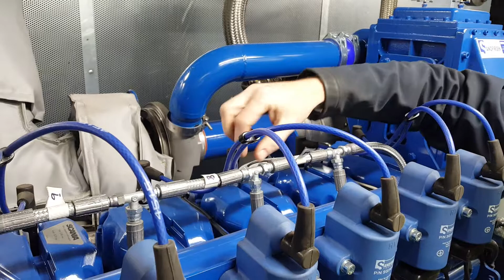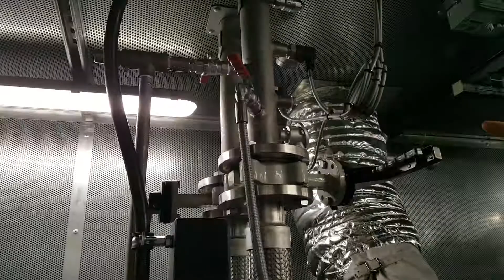Another thing here is the ventilation on the cylinder heads. It came with plastic, but we've done this in steel, and it vents up into the jacket water system. That means there's constant flow, so you can't have an air build up in the heads, so the heads can't run dry. And of course we have protection on the jacket water through the transducer.